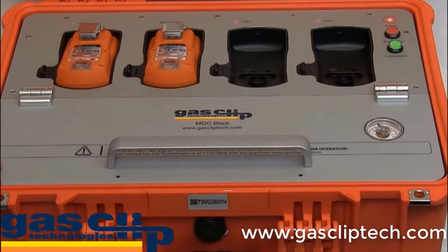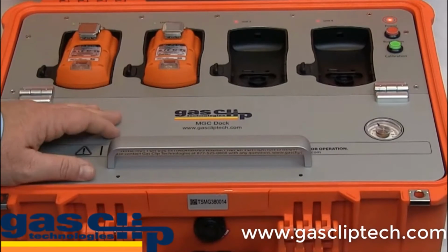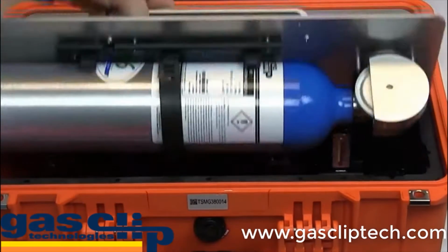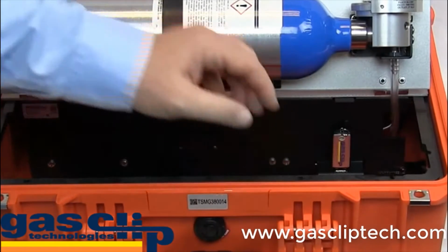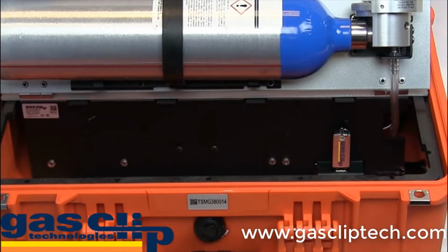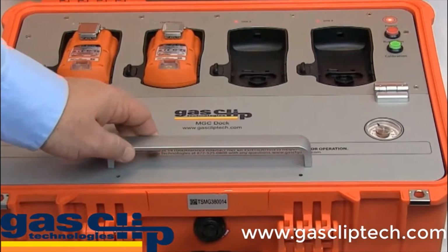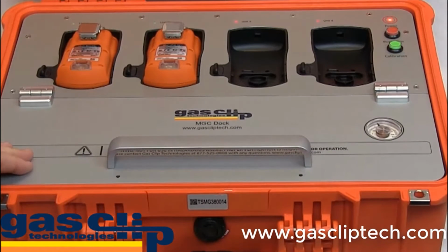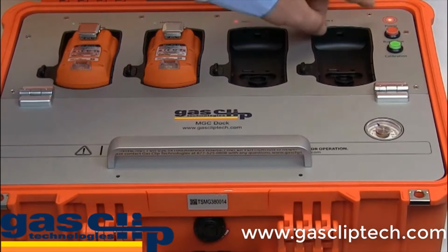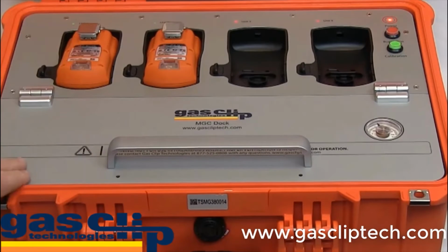Now this is in a purge phase. During this phase, all the data from the monitors will be downloaded to the provided USB data stick. The information on the data stick will give you your date, time, serial number of the monitor, the type of test that you ran, bump test or calibration, and the results, either pass or fail, for all your compliance training. Once the power light goes green, the monitors are ready to use.